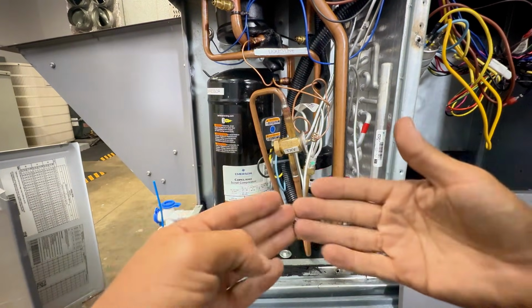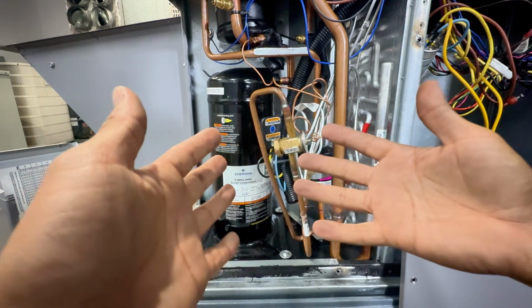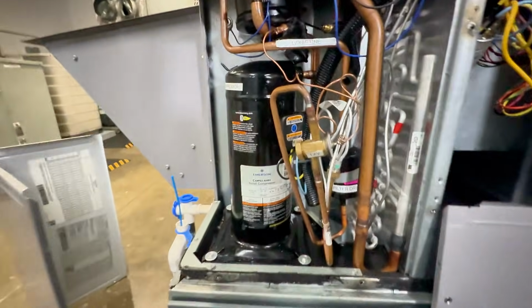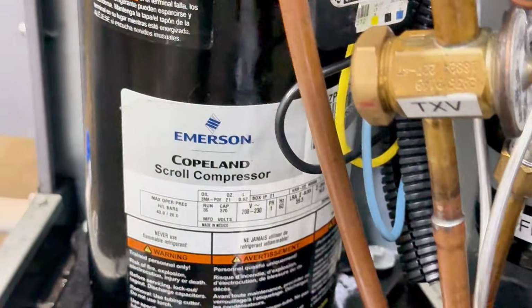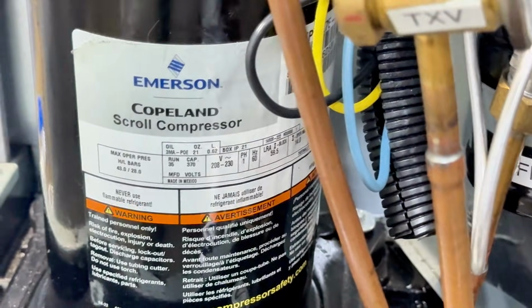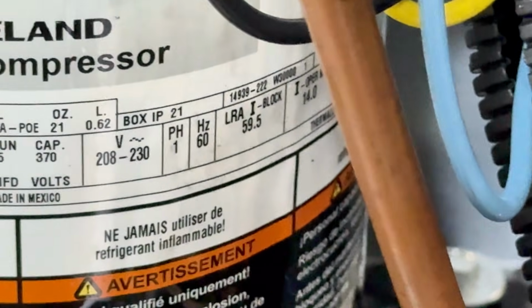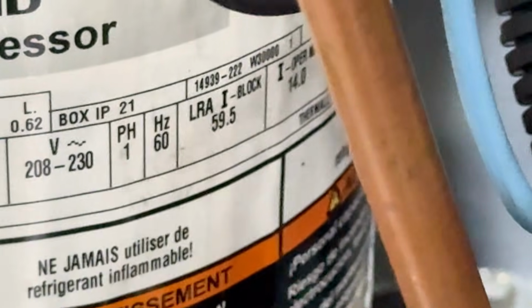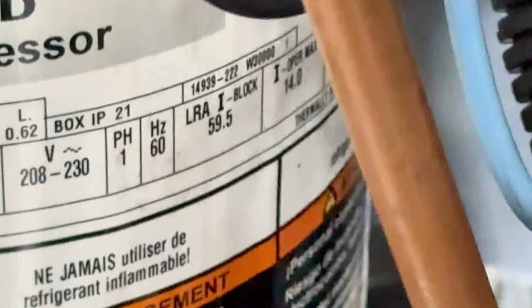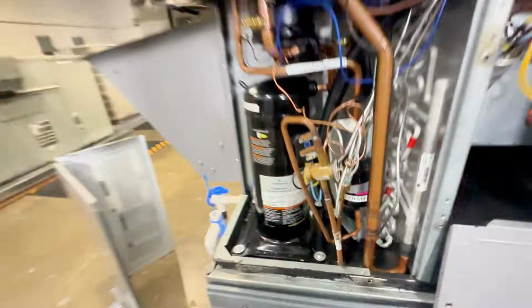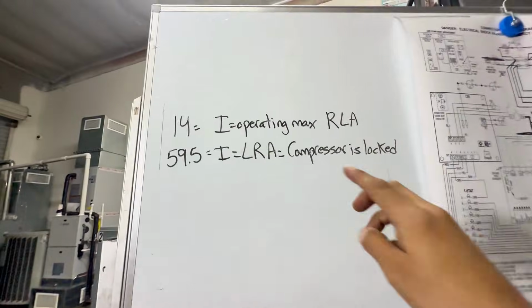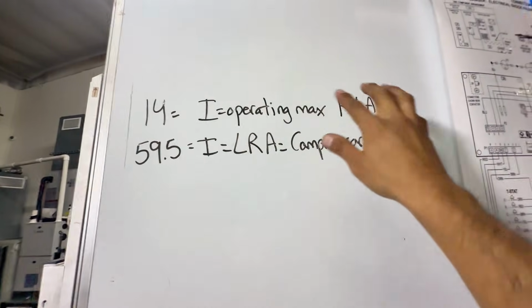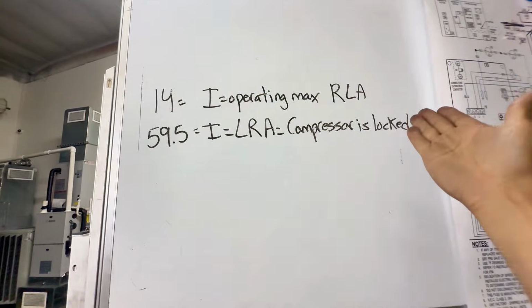All right, so now let's check the current, the amp draw of the compressor. So there's a couple of things we want to keep in mind. We want to kind of write down on the side. So let's see if we can see that there. You see locked rotor amps, 59.5, and then operating max, it says 14. So I kind of wrote that down right here, right? So this is my rated load amps. Of course, it didn't say that, but it's telling you how much it should be pulling, 14 amps.